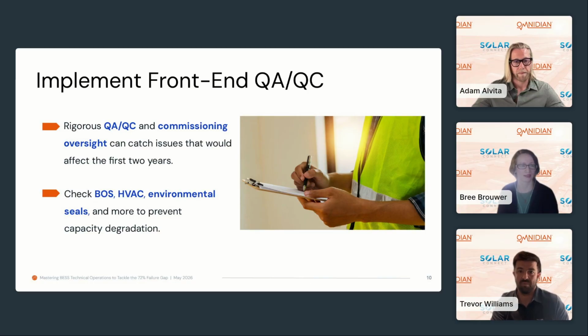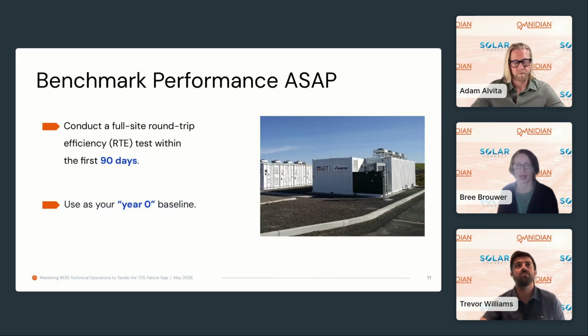Okay, great. So we talked about QA/QC and commissioning oversight. Now let's talk about benchmarking your performance. Do it immediately. Perform a post-commissioning performance benchmark. Do a full site round-trip efficiency test within the first 90 days. This should be used as your year zero baseline to measure the 3 to 30% capacity loss that can occur over time. Adam or Trevor, why is this so important for performance and ROI tracking? What can go wrong if you don't set up a year zero baseline?